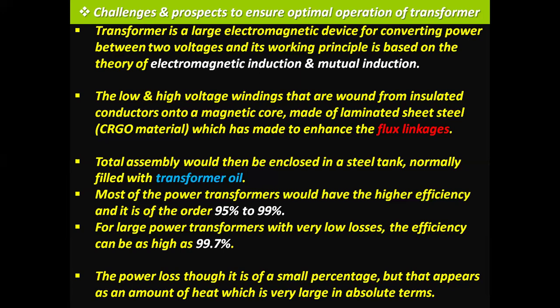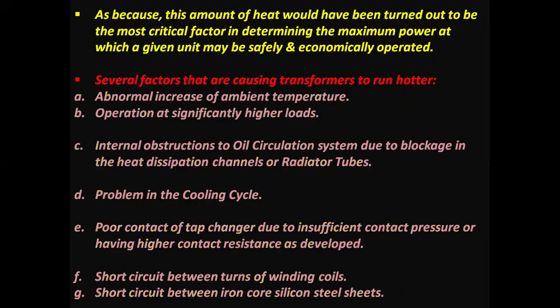The total assembly would then be enclosed in a steel tank, normally filled with transformer oil. Most power transformers have higher efficiency, of the order of 95% to 99%. For large power transformers with very low losses, the efficiency can be as high as 99.7%. The power loss, though a small percentage, appears as an amount of heat which is very large in absolute terms. This heat turns out to be the most critical factor in determining the maximum power at which a given unit may be safely and economically operated.